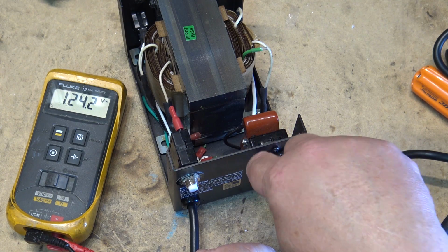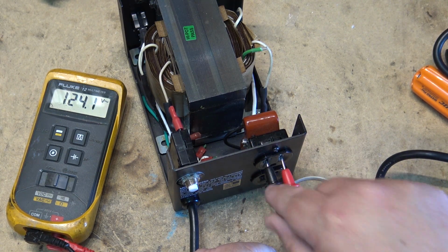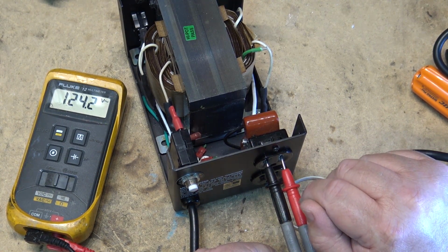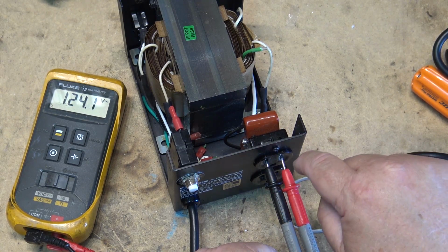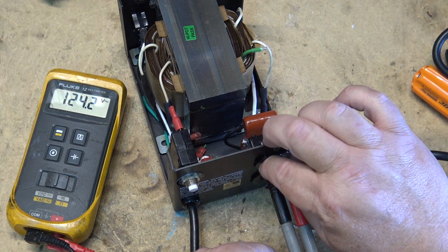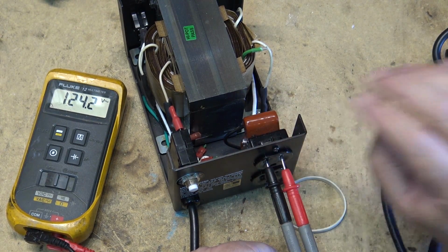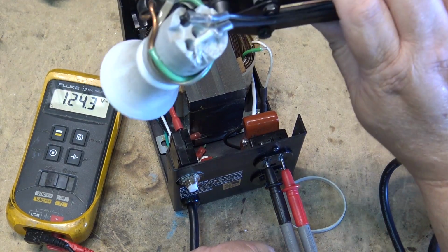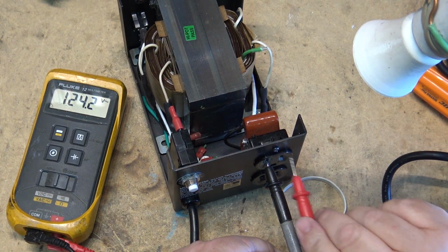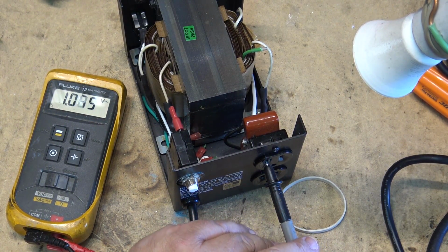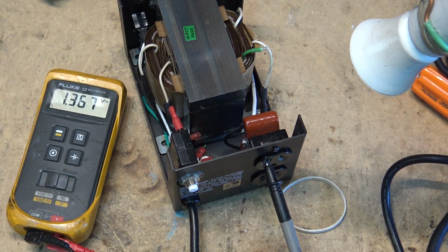If I put my finger down between the two of them, yes, I'm going to get a shock for sure. But if I touch either one, the hot side or the neutral side, to ground, because there is no ground, even touching something grounded like this lamp arm, I can take my meter and measure to ground.